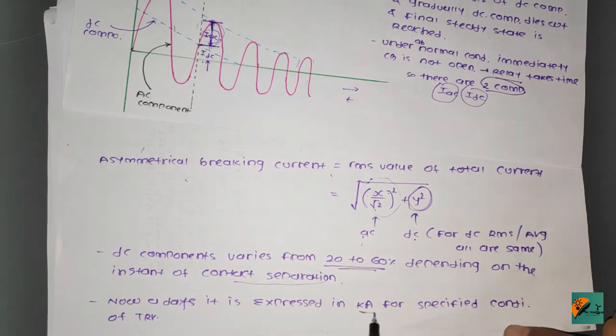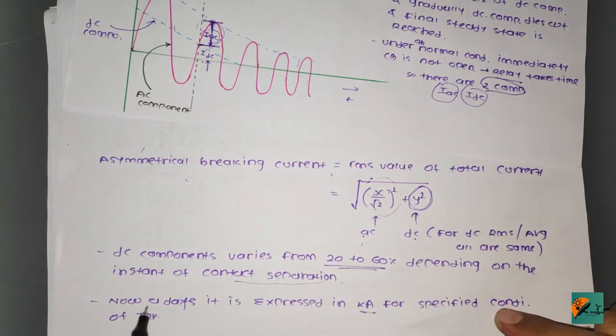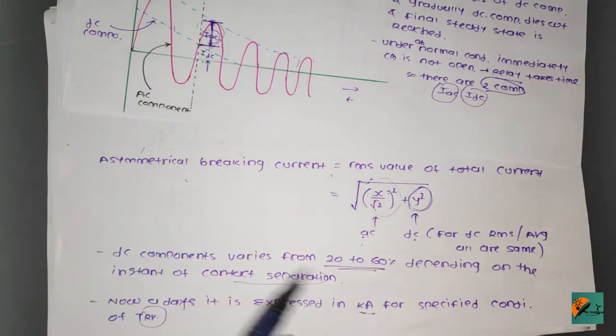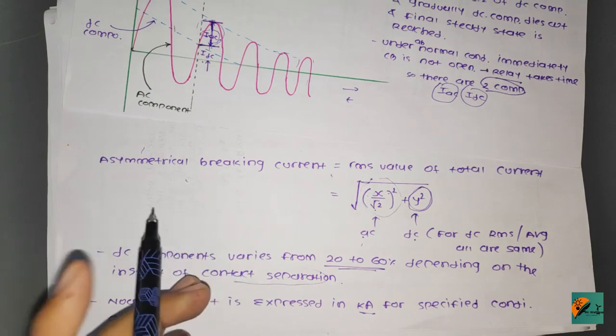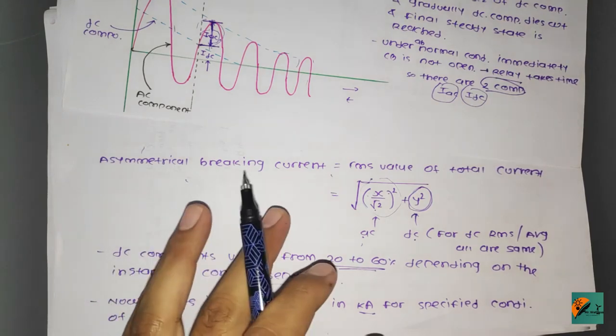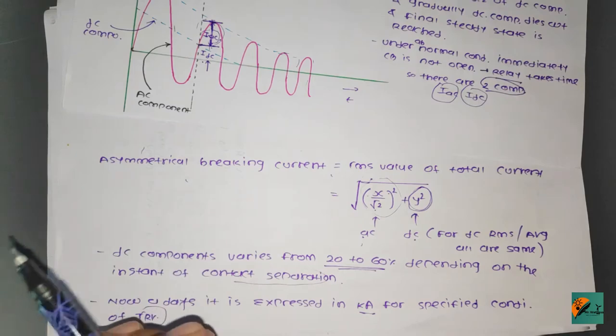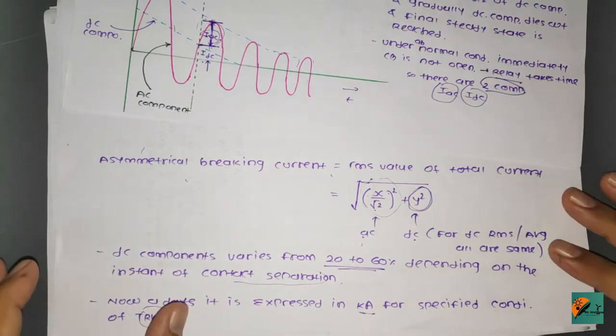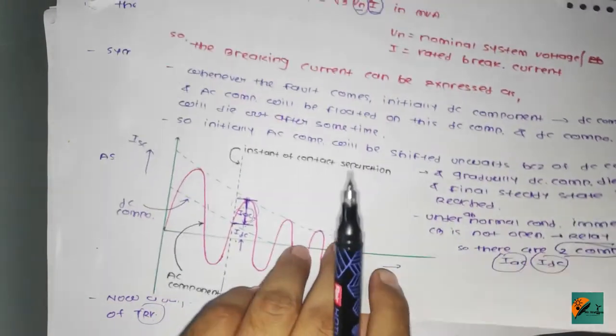Nowadays, the breaking current is expressed in kiloamperes for a specified condition of transient recovery voltage. In earlier days it was expressed in MVA so that fault levels could be determined, but now kiloamperes is the standard. This is all about the rated short circuit breaking current.